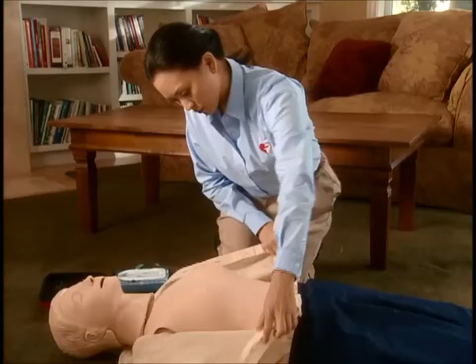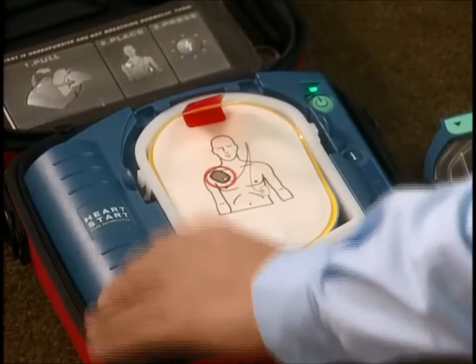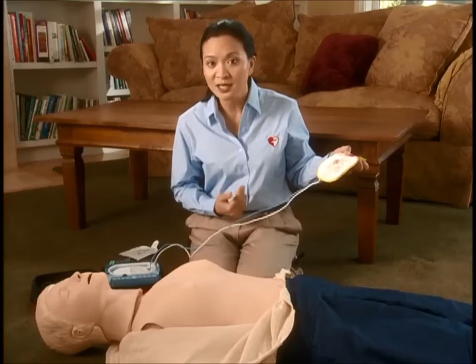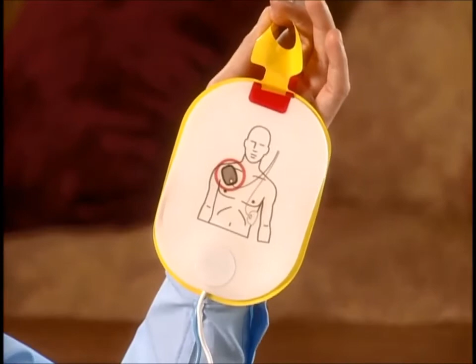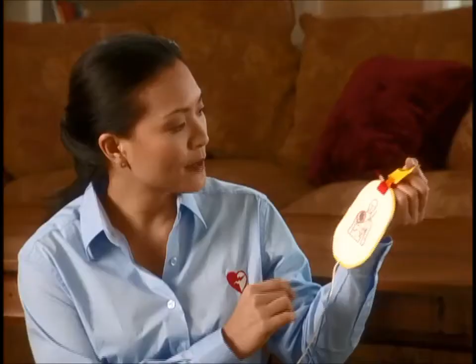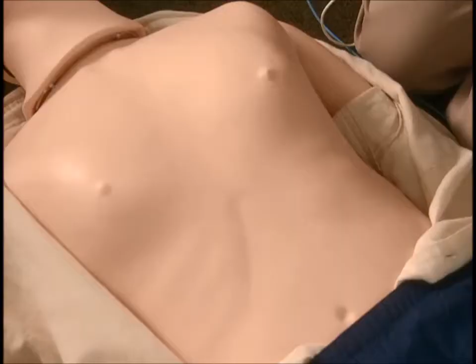When the patient's chest is bare, remove the protective cover and take out the white adhesive pads. Now, peel off the film seal on the pad's cartridge. Remove the pads. They're already connected to the defibrillator, which senses when you remove the pads and will continue to guide you. Look carefully at the pictures on the white adhesive pads. Peel one pad from the liner and place it exactly as shown in the illustration. It doesn't matter which pad is placed first. Press the pad down firmly to ensure good contact with the skin. Repeat with the other pad.